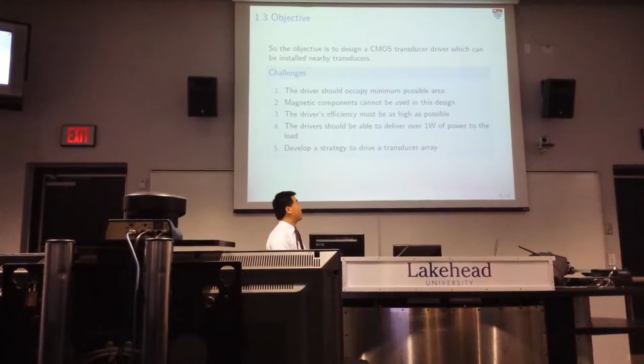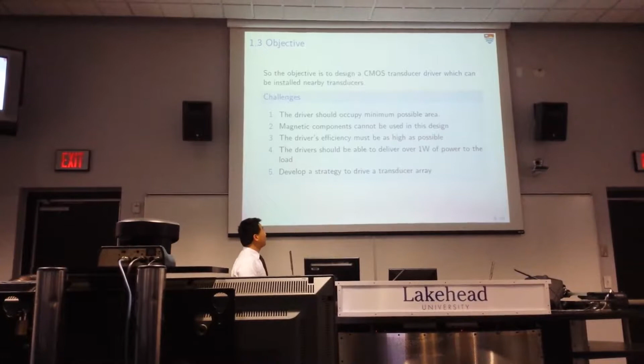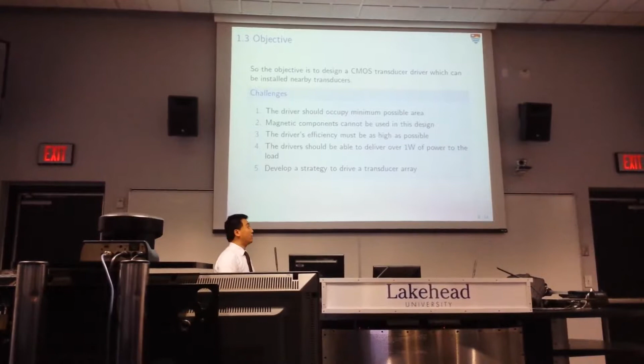There are some challenges. The first one is the driver should occupy the minimum possible area because we don't have a large portion of area near the transducer. And the second one is that magnetic components such as inductors and transformers cannot be used in this design because they will interfere with the MRI operation. And the third one is the driver's efficiency must be as high as possible to avoid overheating. The fourth one is the driver should be able to deliver over 1 watt of power to the load. And the last one is we must develop a strategy to drive a transducer array.